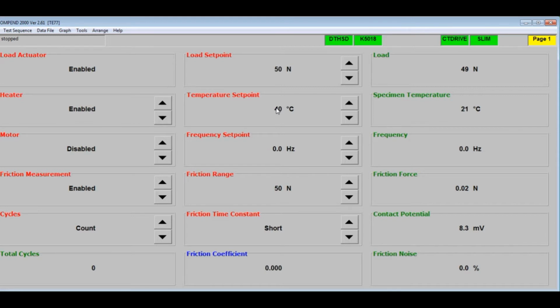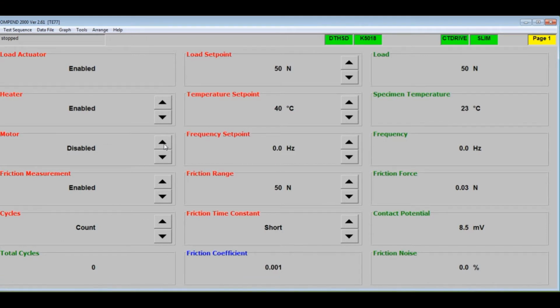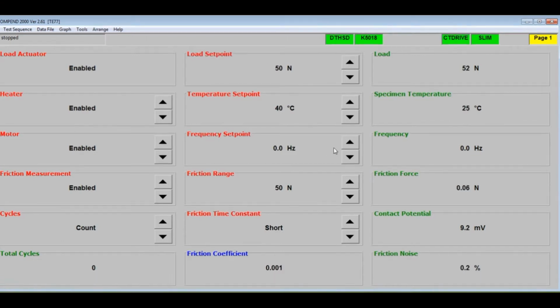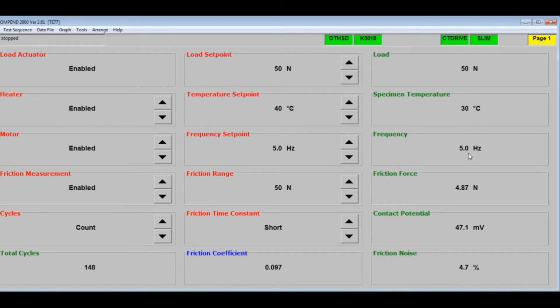Having first confirmed that the test specimens have been fitted and the loading yoke has been engaged, the motor can now be enabled by clicking the up arrow on the red motor box. The frequency set point box can now be used to set the reciprocating frequency in just the same way as the other set points. The measured frequency is displayed in the green frequency box and the number of cycles in the green total cycles box. The count can be reset to 0 by pressing the up arrow on the red cycles box. This is a momentary action switch, and the display will revert to count after a few seconds.